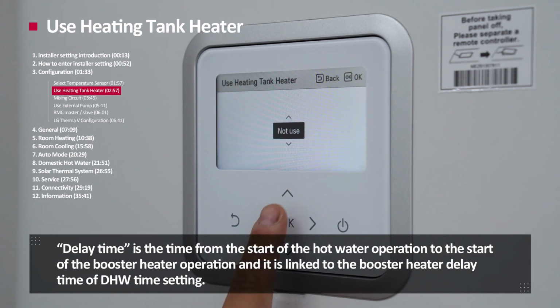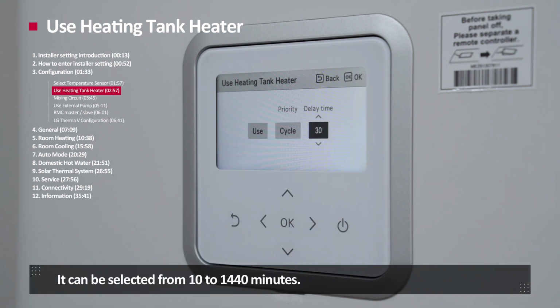Delay time is the time from the start of the hot water operation to the start of the booster heater operation, and it is linked to the booster heater delay time of the DHW time setting. It can be selected from 10 to 1440 minutes.